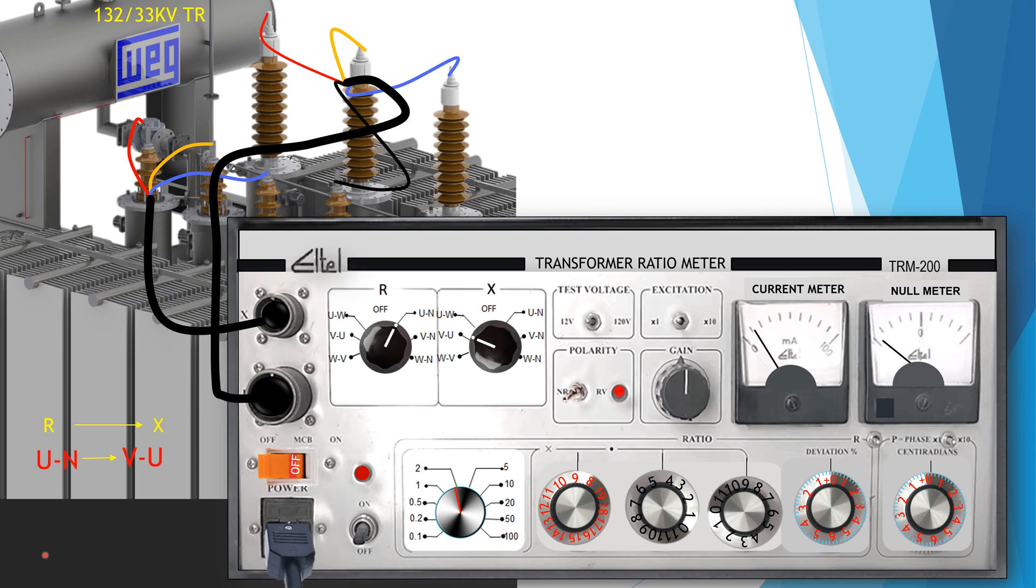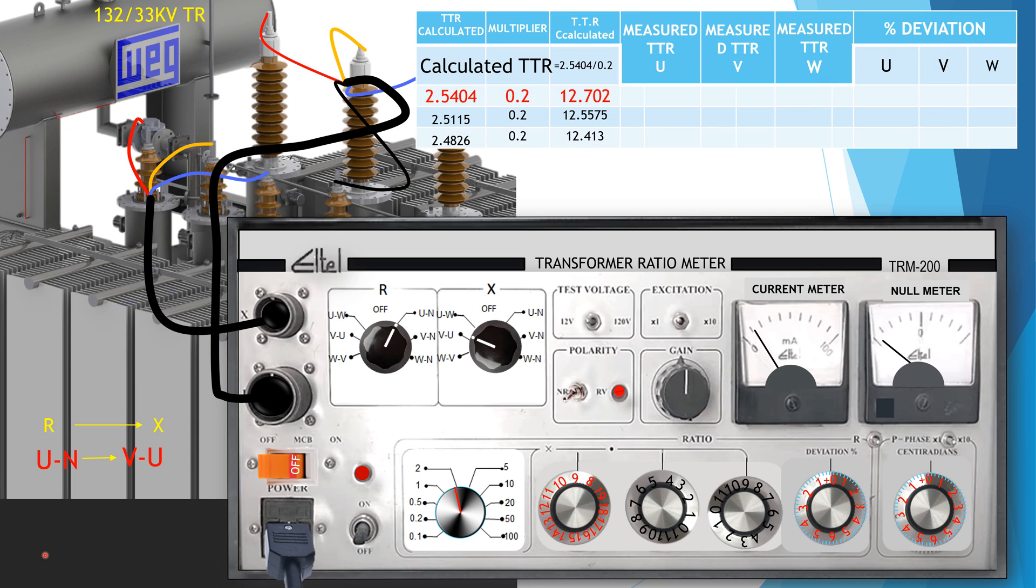Through this testing procedure, now we shall find the percentage deviation of TTR. To calculate TTR against which testing is conducted is 2.540 divided by 0.2 is equal to 12.702. The whole number here is 12, first fraction is 7, and second fraction is 0. Now watch the testing process.